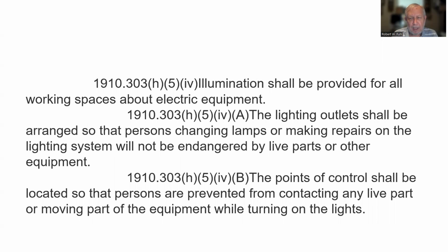Illumination shall be provided for all working spaces about electrical equipment. The lighting outlets shall be arranged so that persons changing lamps or making repairs on lighting systems will not be endangered by live parts or other equipment. The points of control shall be located so that persons are prevented from contacting any live part or moving part of the equipment while turning on the lights.